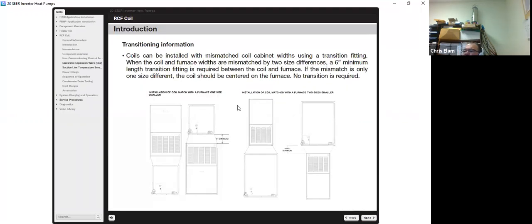Transitioning. It's not uncommon to have a smaller furnace or a larger coil. Coils can be installed with mismatched coil cabinet widths using a transition fitting. When the coil and furnace widths are mismatched by 2 sizes, a 6-inch minimum length transition fitting is required between the coil and the furnace. If the mismatch is only 1 size, the coil should be centered on the furnace. No transition is required.